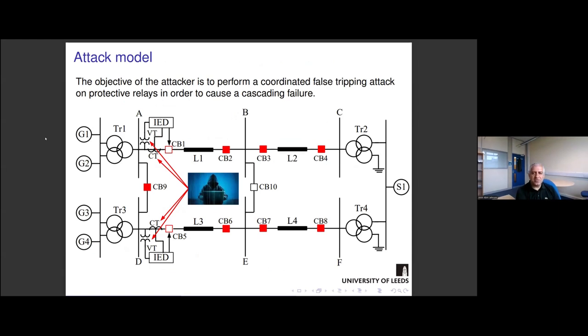The objective of the attacker here was to perform coordinated false tripping attacks on protective relays in order to cause a cascading failure. We assume that the attacker tries to get access to the VT, CT, or the merging unit that exists in the substation, and by falsifying the data, tries to force the IED or protective relays inside the intelligent electronic devices to send a falsified command to circuit breakers and open them and force the transmission lines to go on outage. And if they succeed in tripping more than one transmission line, because normally power systems are secure to N-1 security, they can easily cause a cascading failure in the system.